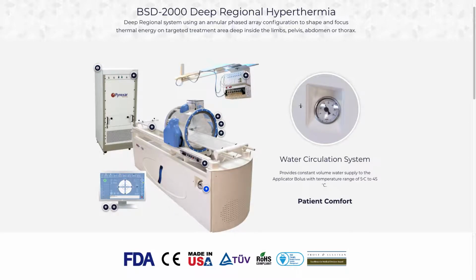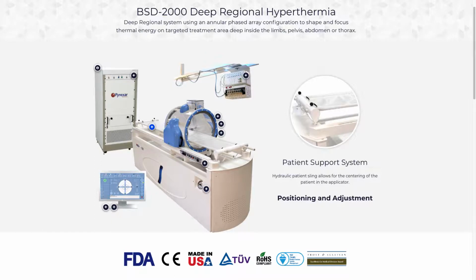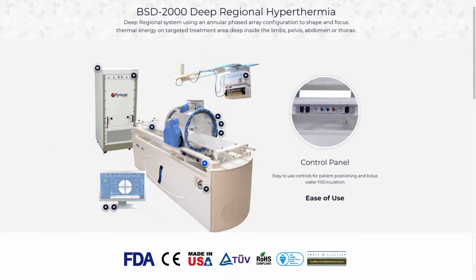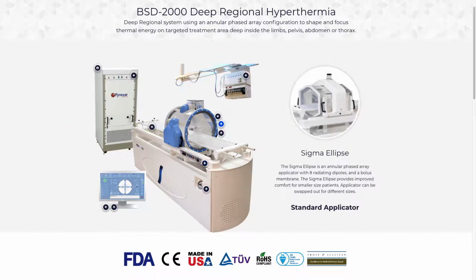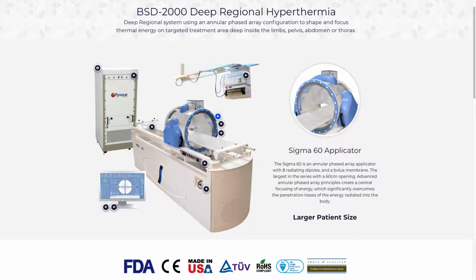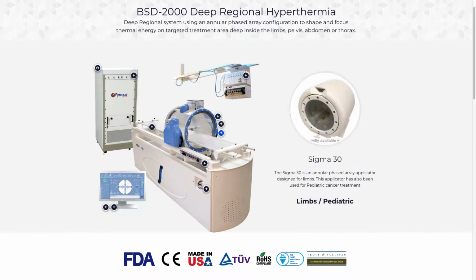Let's start with the BSD-2000 Sigma base. The base contains the water storage tank, circulation and drain system for deionized water. Circulation pumps integrated with the water heating and chilling system provide a temperature-controlled bolus for patient comfort, and lifted in place using a built-in hydraulic system. The BSD-2000 offers 3 patient applicators. The Sigma Ellipse is an annular phased array applicator with 8 dipole antennas that surround the patient. The Sigma 60 applicator has a 60 centimeter opening designed for larger patients, and the Sigma 30 designed for treatment of the limb and can be used for pediatric patients.